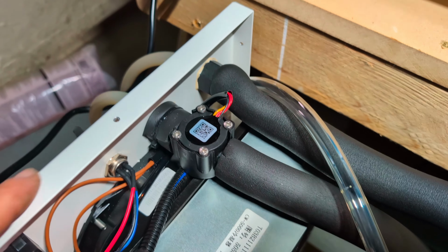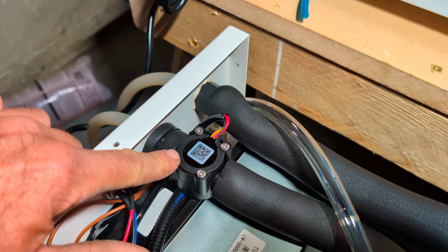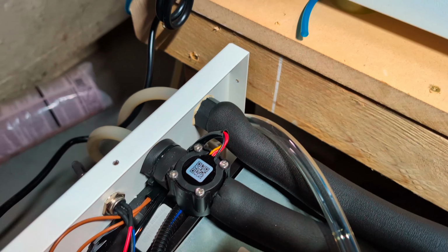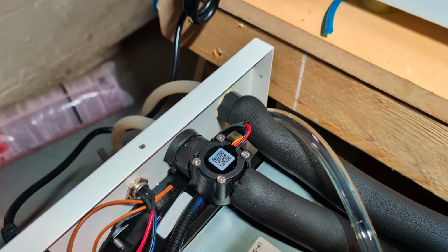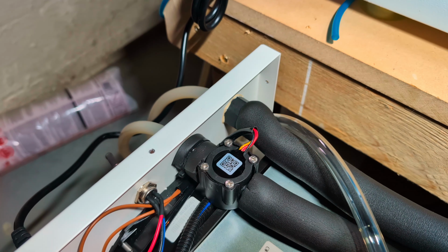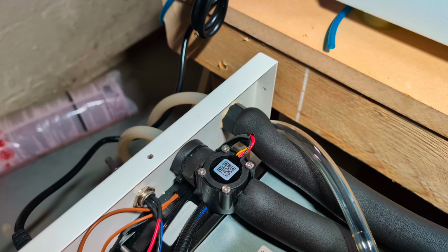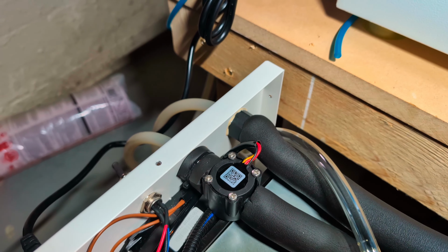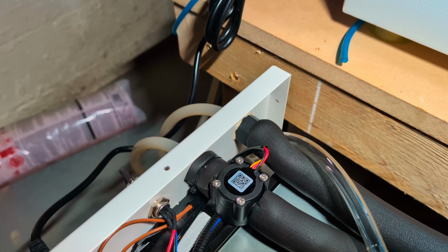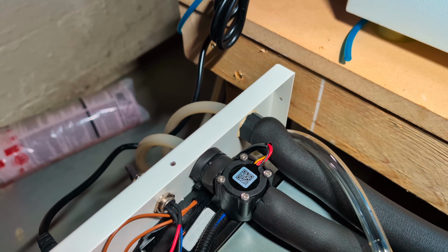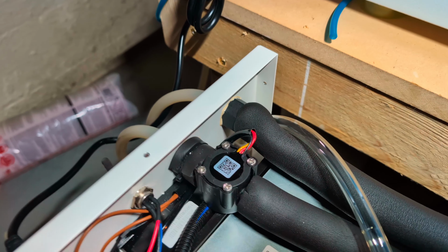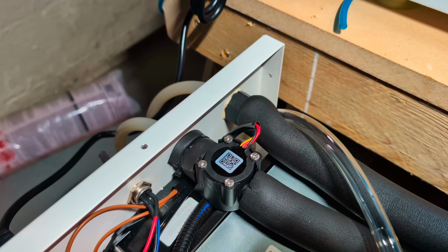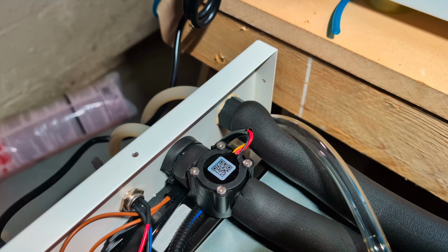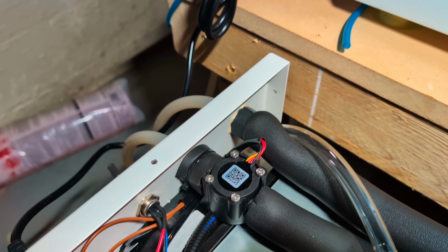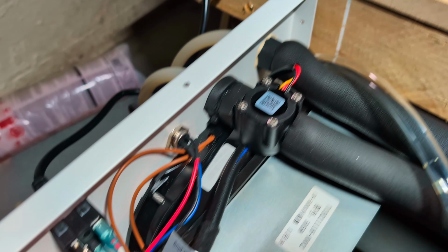The first thing that you can do to check to make sure that the flow switch is working, take the 4 screws out. The top of the flow switch will come off, and what will be exposed is a little paddle flywheel that the water flows through. Just make sure that that spins freely, and if it does, then the problem is probably with the actual electronics of the flow switch.